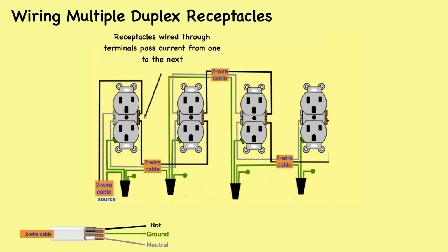When wiring multiple receptacles in a row, it is crucial to understand how the current flows from one outlet to the next. Receptacles wired through terminals utilize the terminal screws to pass the voltage from one receptacle in series to the next one. In this diagram, we have four 120 volt 15 amp residential electrical receptacles wired in a row. Each receptacle is connected to the next one using terminal screws, creating a continuous flow of current through the circuit.